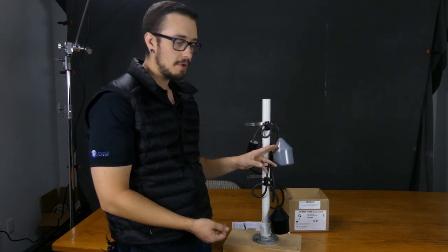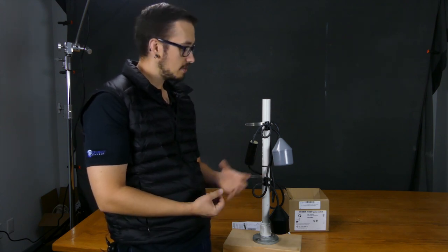When it comes to these types of switches you've got two design choices to make: do you want a mercury switch or do you want a mechanical switch? Unfortunately both are rated for non-potable water applications, though if I had to use one in potable water, not recommending it, I would definitely use the mechanical as opposed to the mercury. Some folks like the mercury but it does seem like the way the world is taking us away from the mercury switches and more things and applications are using the mechanical switches.